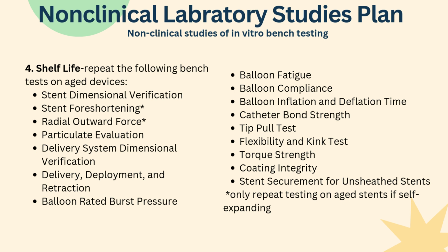So for the stent itself, we reassess dimensional verification, foreshortening, radial outward force, and particulate generation to confirm that the mechanical integrity and the deployment characteristics are maintained over time. We will also repeat delivery system testing, which will include dimensional verification, delivery, deployment, and retraction. And again, this will be to ensure that the system remains reliable after aging. Now, the balloon specific testing, such as the rated burst pressure, fatigue, compliance, inflation and deflation time, all of that will help confirm that the balloon performance is also not compromised with storage. Some additional catheter and system level tests, including bond strength, tip pull, flexibility and kink resistance, torque strength, coating integrity, and the stent securement, will also ensure that the delivery system remains robust and safe throughout its shelf life.